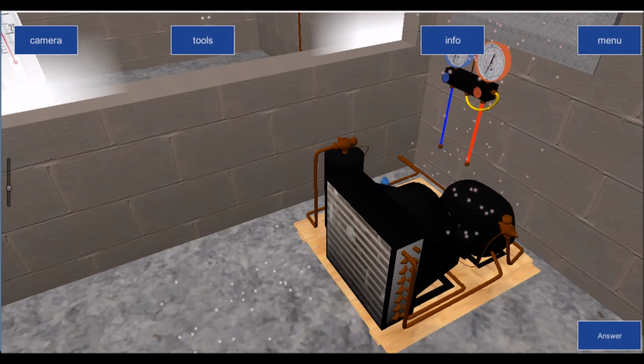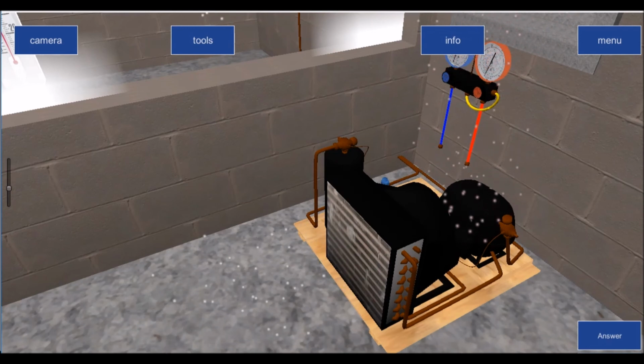Now, I hear what you're saying in terms of it might be slightly wrong, or it is wrong, because if we had a fouled heat exchanger here, in fact, you'd find that your condensing temperature will be excessively high because you don't have sufficient air going across. So if you had 20 degrees going across and it was because it was all blocked up, in fact, the opposite would happen, you wouldn't have an 18 degree condensing temperature here. The only time that you could find yourself with an 18 degree condensing temperature is if the compressor itself wasn't pumping, or there wasn't any superheat built up inside in your discharge. So you're right, that's an actual bug in terms of the problem. The problem that we should have had, instead of 18 degrees, that should have been maybe 58 degrees or 48 degrees or something like that, rather than 18 degrees.